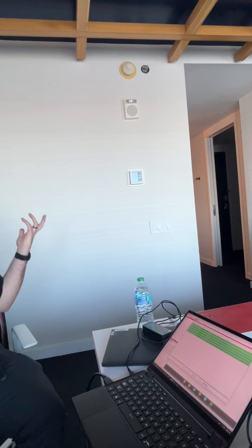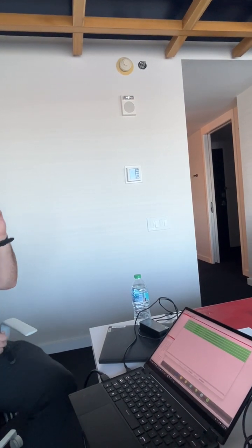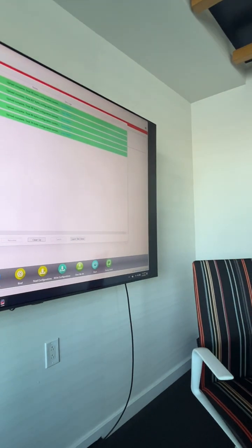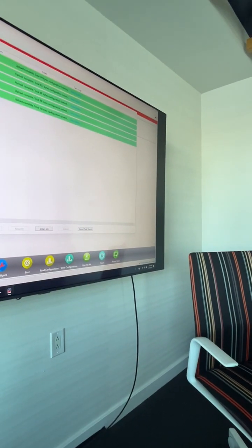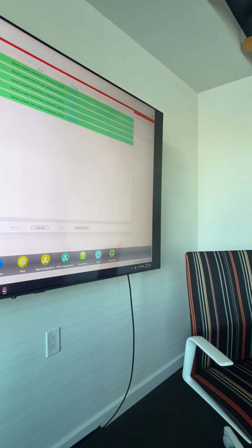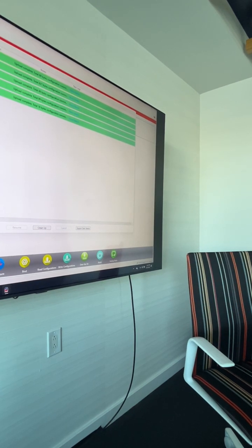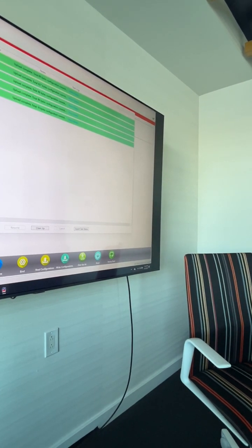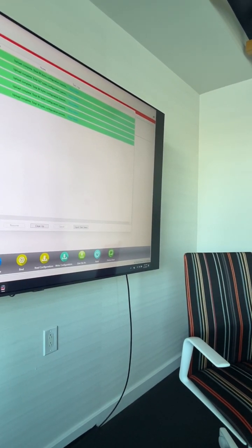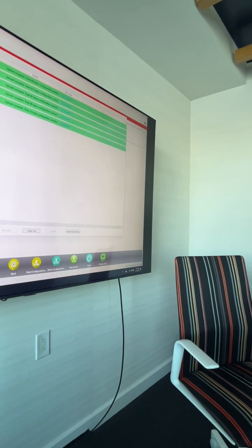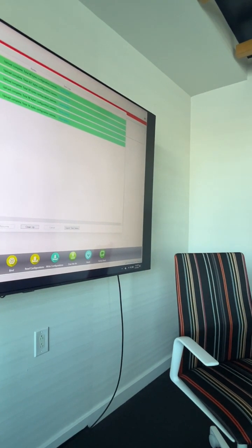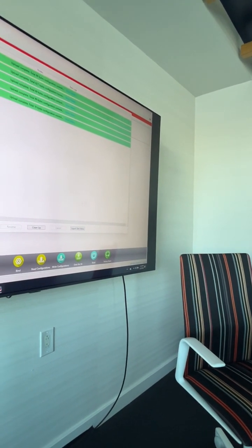Go to a low enough temperature to cool, and make sure it's cooling. How could we confirm that it's also working with the PMS? Let's say a room is checked in. If you go to a room that just checked in, it should be at 72 degrees as the set temp. Is there a way to also look on the server to make sure it's seeing that? You can look at trend data and see.